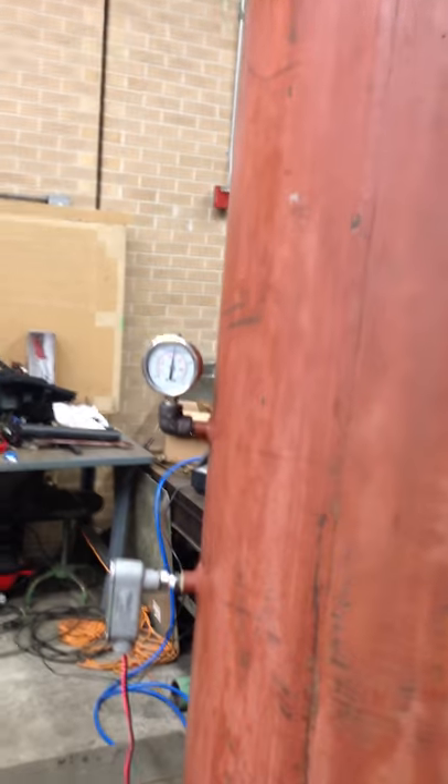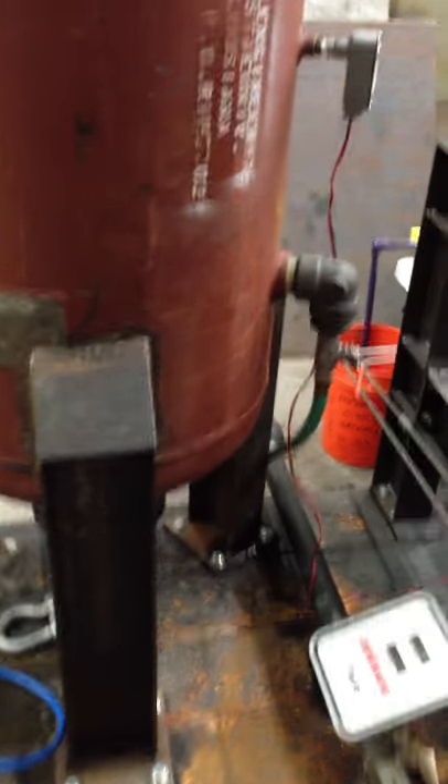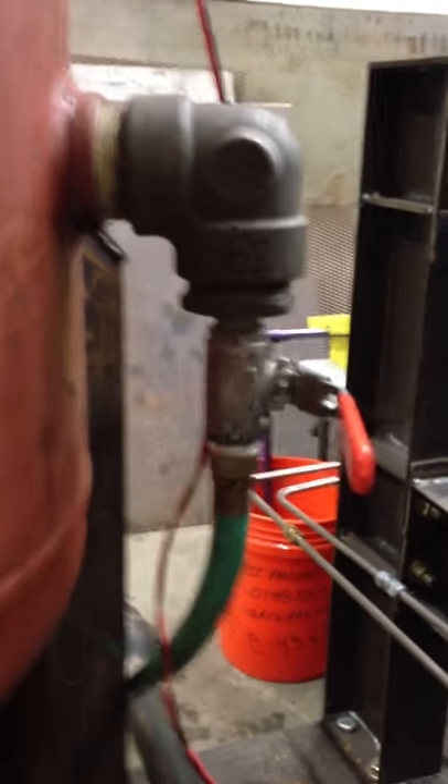That's Miles, hard at work collecting data. We modified this pressure vessel — it was a coated vessel. We derated it and established a new maximum allowable working pressure of 330 PSI. We hydro-tested it at 500 PSI, and we have a relief valve set at 300 PSI to protect the tank from exploding. We have a fill valve to fill it with water.